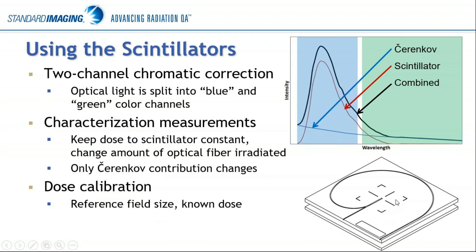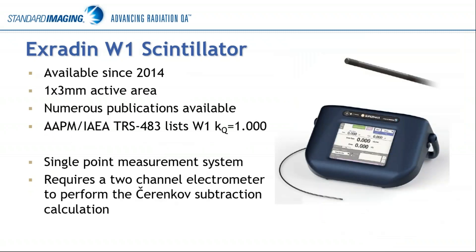You can then do a dose calibration. The slab for the W1 shows a 10x10 field marked with the minimum fiber configuration — give it a known dose at a known depth — and you can then report your measurements in terms of the dose that the scintillator is receiving. The W1 scintillator, as I mentioned, is our first generation device. It has been on the market since 2014, has a 1x3 millimeter active area, and there are quite a few publications about its use and response listed on our website.